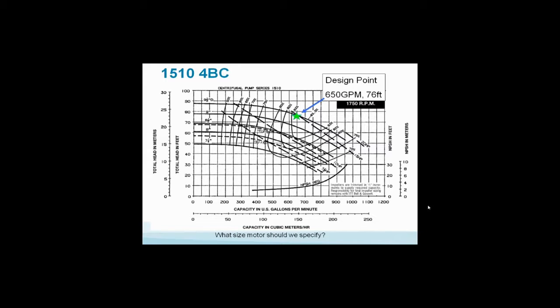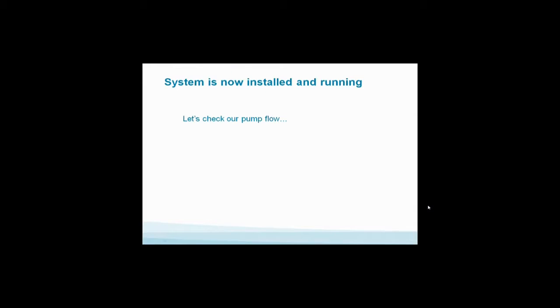So what size motor should we specify? By the way, I think I'd put a 20 horsepower on this to be non-overloading. So the system is now installed and running. Let's check out the pump flow. Let's see what really happened.